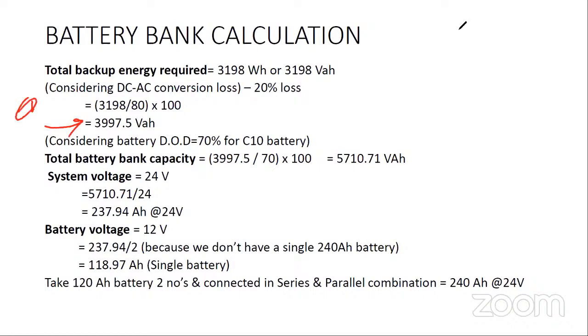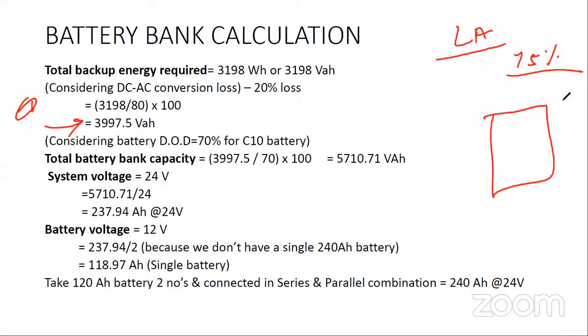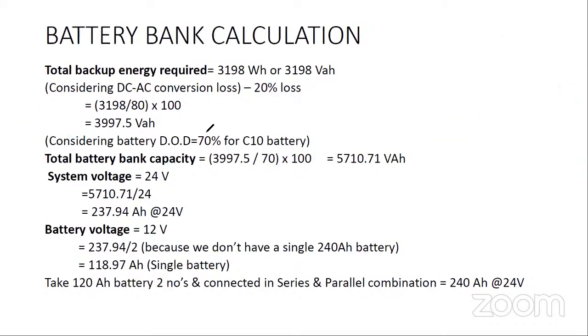Now, for a lead acid battery, the depth of discharge should not be more than 75%. Out of 100% of the battery you can discharge up to 75%, but the 25% should remain as residual energy inside the battery to maintain its health. So again I'm considering 70% as the worst case for my analysis. I'm considering 70% DOD for a C10 battery. If that is the case, then 3997.5 is the 70% capacity.